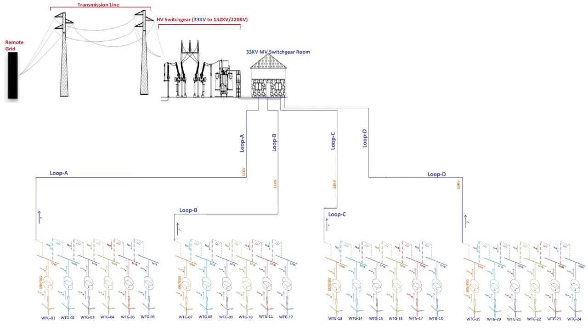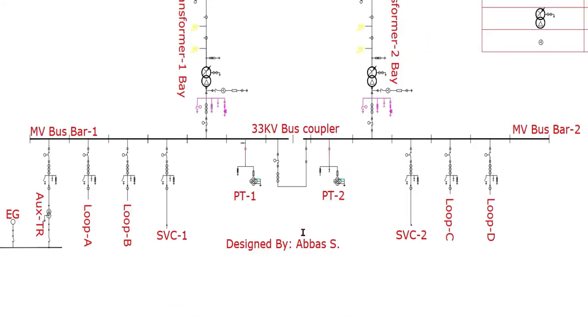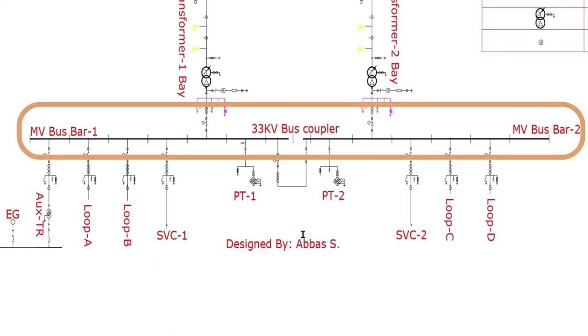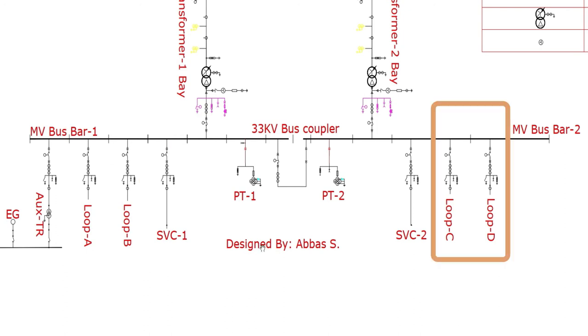I will explain the layout of a typical wind farm with this string diagram. I have also attached this string for your reference. The loops are connected to the MV busbar. An electrical busbar is a conductor strip used for collecting power from the incoming feeders and exporting to outgoing feeders. In a wind power plant, two MV busbars are installed for redundancy. Loop A and loop B are connected with busbar 1, and loop C and loop D are connected with busbar 2.